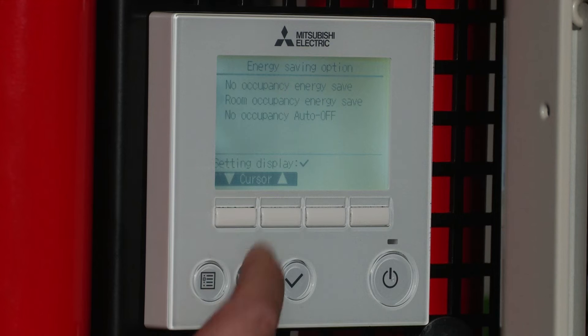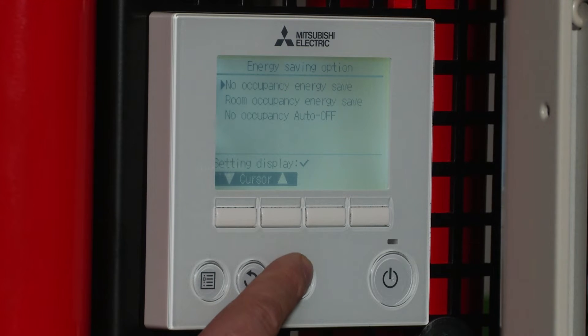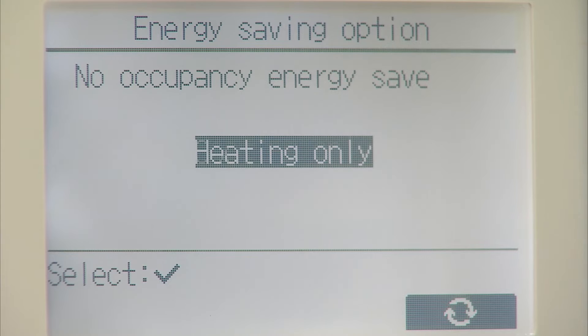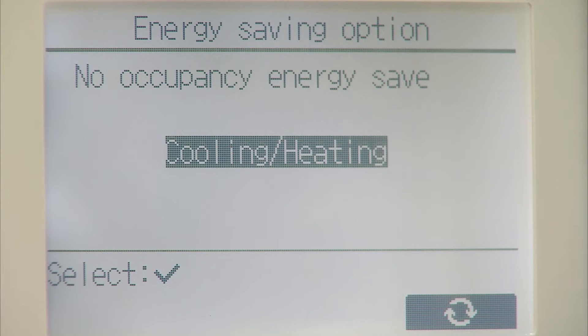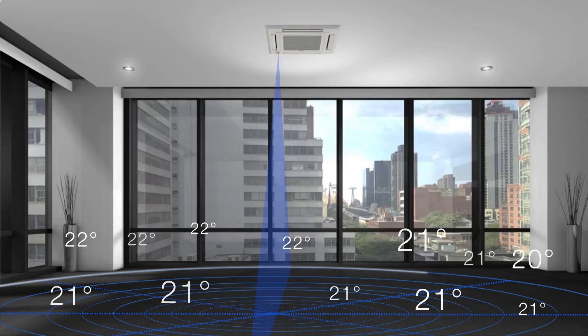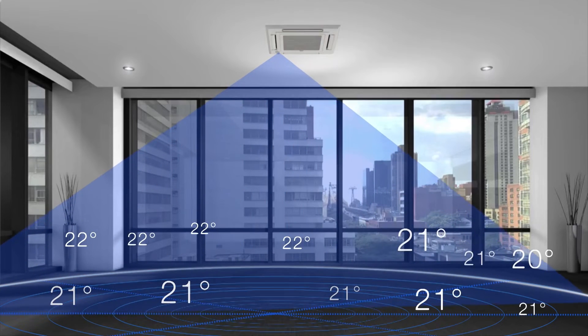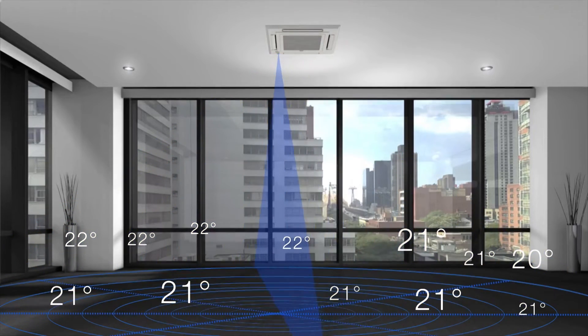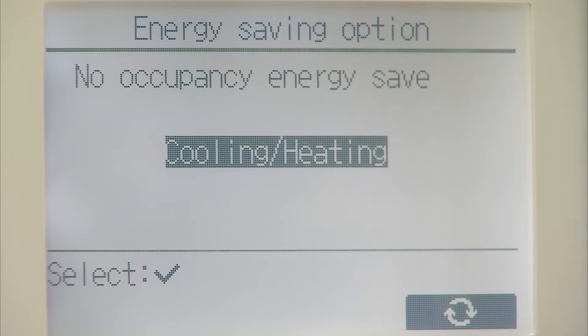Select the no occupancy energy saving option. I'm going to select heating and cooling. What the unit will do now is sweep the room with the infrared camera, looking for occupancy. If it doesn't see an occupant for an hour, rather than the unit being off, it will put it to a two degree offset. When it does recognise somebody in the room, it goes back to the actual room temperature.